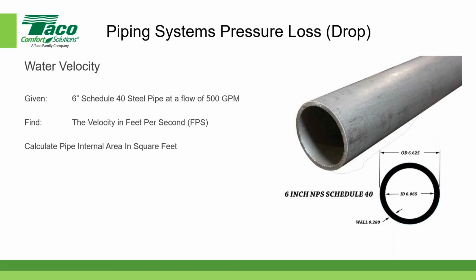If you notice on the right-hand side, it says the inside diameter of this pipe is 6.065 inches. Even though the pipe is 6-inch Schedule 40, the outside diameter is 6.625 inches, but the inside diameter is 6.065. And this is called Schedule 40 pipe or standard pipe.